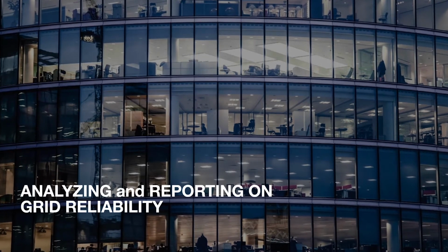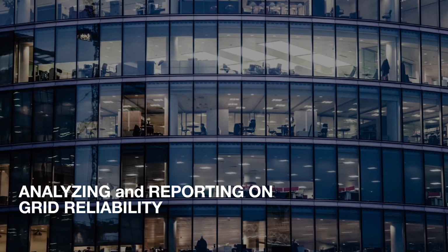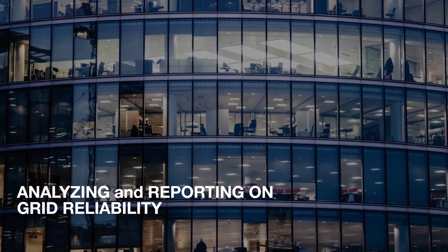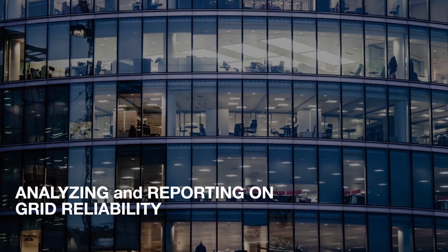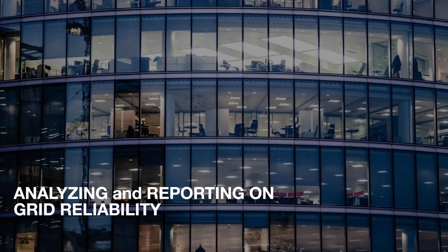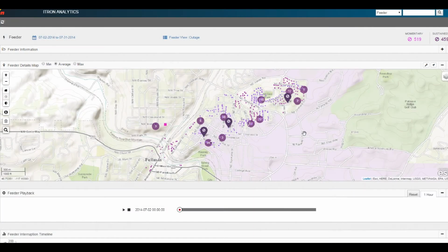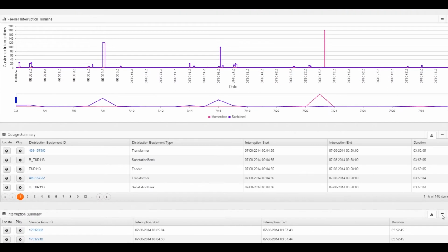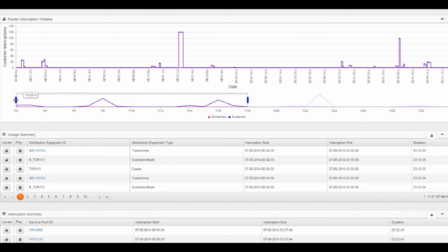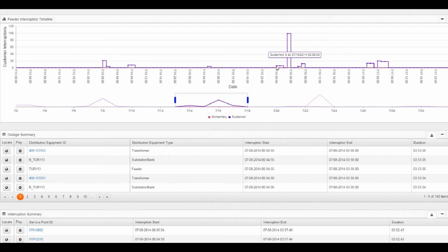In this scenario, we'll examine the grid reliability application, which provides engineers and operators with a summary of outage activity throughout the system and the tools to investigate root causes and the customers affected. Customer interruptions are classified as momentary or sustained depending on their duration and displayed on the system map. GIS connectivity is used to aggregate AMI events to their parent transformer, then to the circuit and the substation depending on the extent of the outage. The worst performing circuits are summarized in a column chart so the engineer can navigate directly to those of most interest.